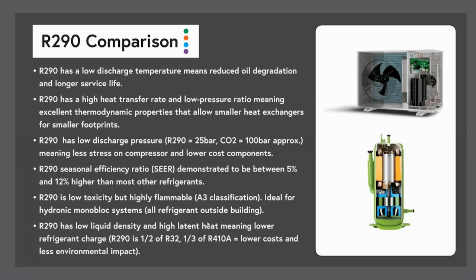Right, so let's have a look at R290 compressors and why they are good compared to other appliances. One of the things R290 is good for is that it has a low discharge temperature, which means it is pretty easy on the oil, and therefore they have long service lives. R290s have been around forever. They've been in small appliances and refrigerators for a long time. So this is really the first time they've entered the home heating and hot water market, but the technology is well known. Low discharge temperatures mean they are pretty easy on the oil. A lot of other refrigerants have much higher discharge temperatures, and high temperatures obviously lead to higher levels of degradation of the oil in the compressor. So they can end up with shorter service lives.